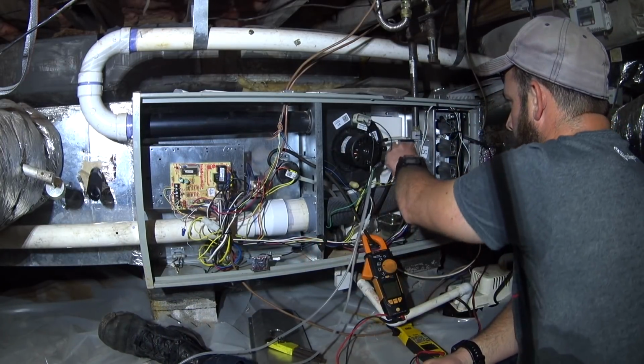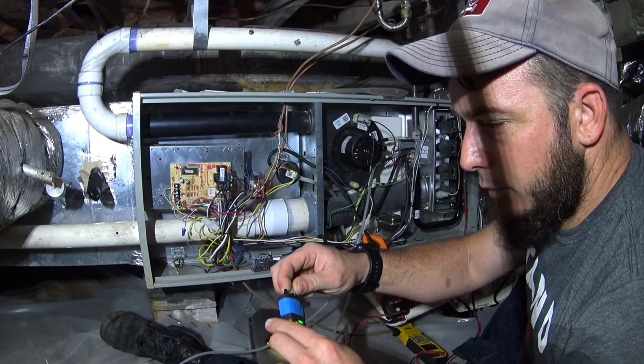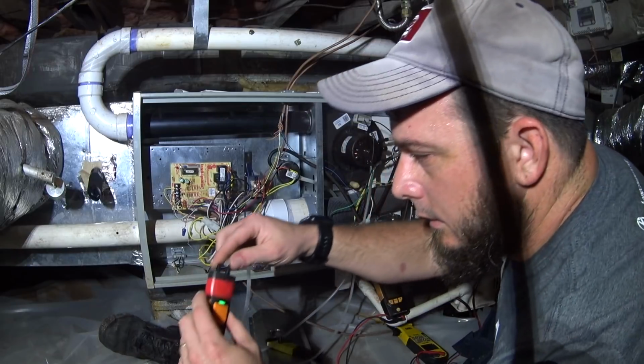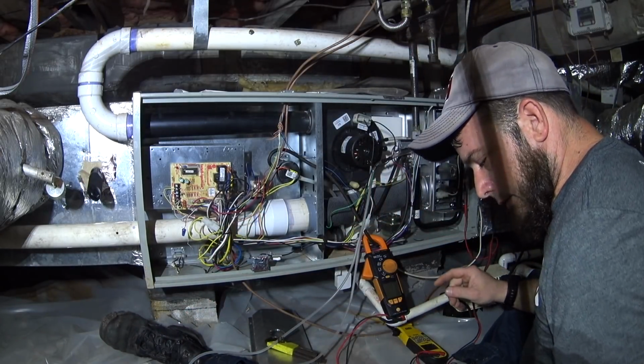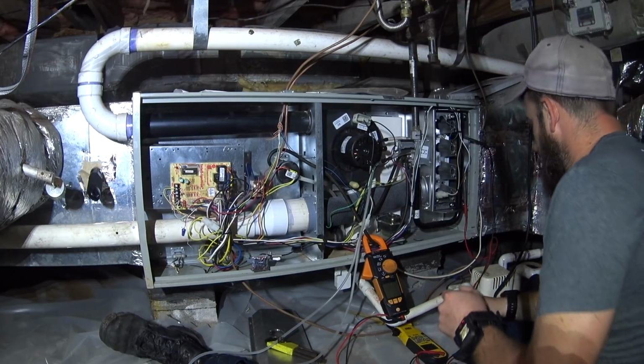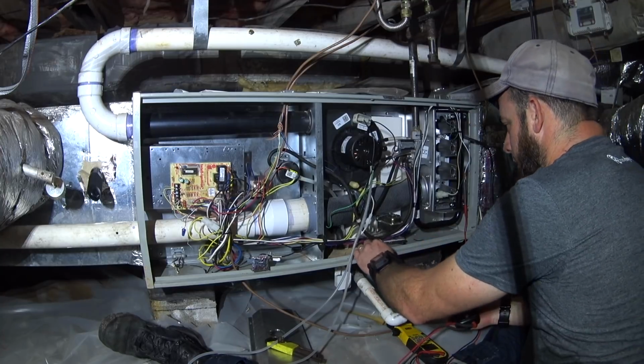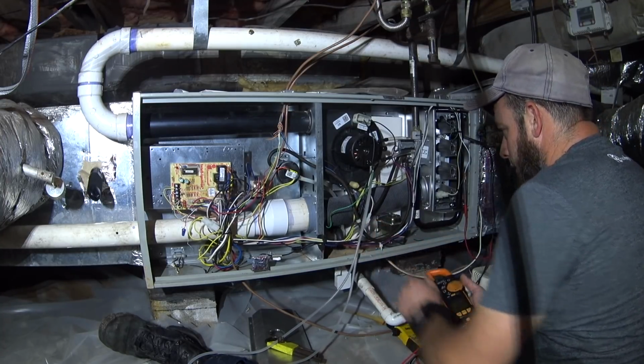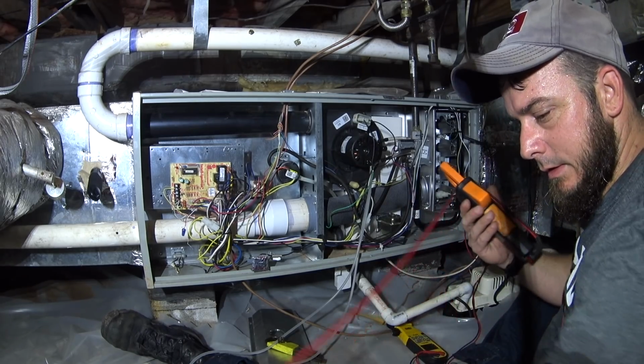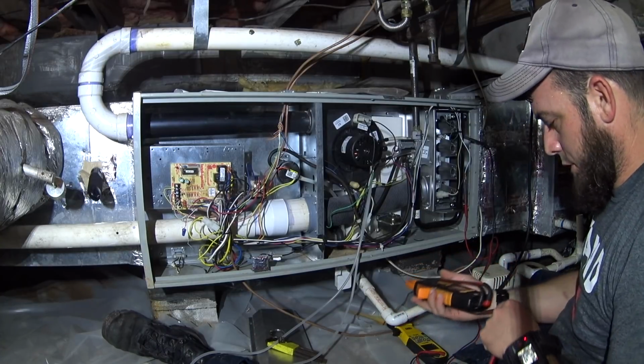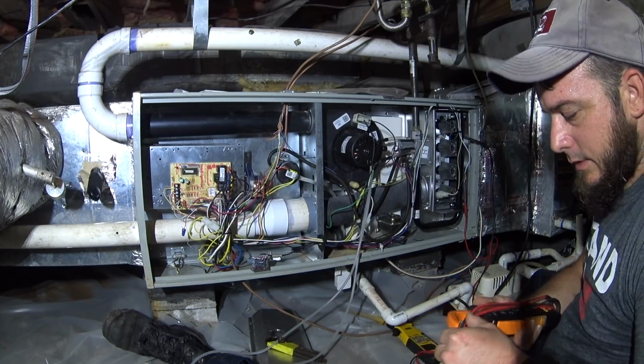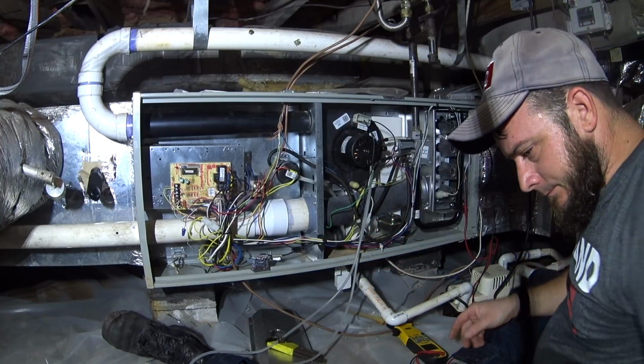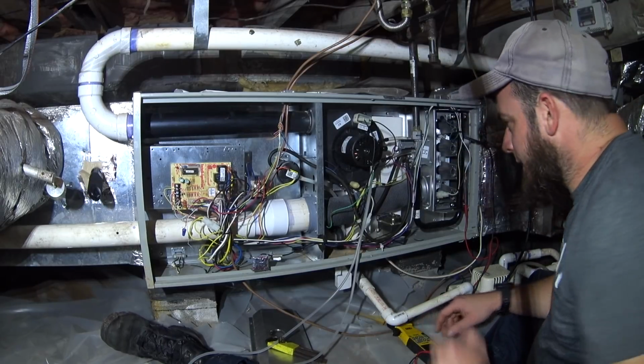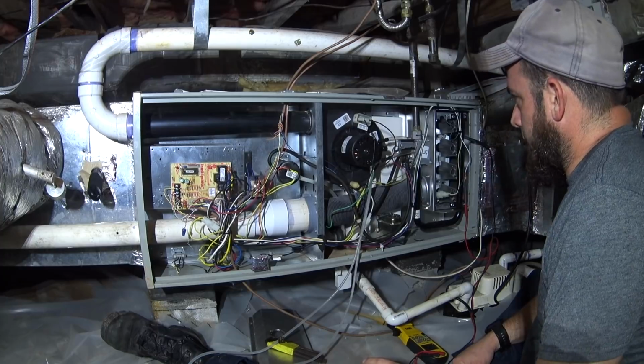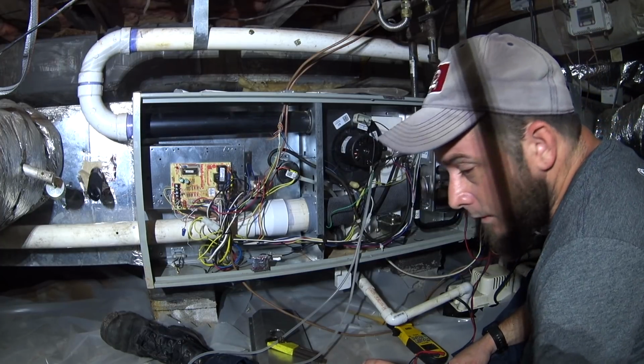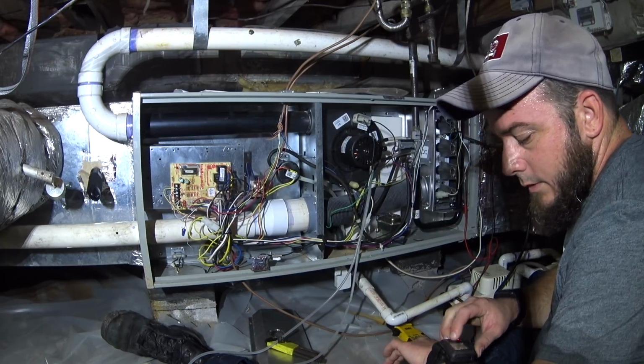Just make sure we've got outlet on the blue gauge and inlet gas pressure on the red gauge. The importance of checking outlet and inlet pressure for gas, at least for me, is mostly just to confirm that the incoming gas pressure is sufficient. I'm already checking gas pressure, so I might as well check both when they are reasonably accessible. Alright, so we're ready for flame signal, gas pressure. And I will be right back.